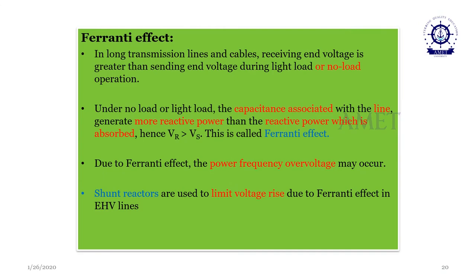Now, due to the Ferranti effect, the receiving end voltage is more than the sending end voltage. So this is a very critical condition for the system, and it has to be taken care of. How to limit this Ferranti effect? Again, as I said, by connecting a shunt reactor, we can absorb that excess power, and in that way we can safely maintain the input side voltage and the output side voltage equal. This is one very simple way.